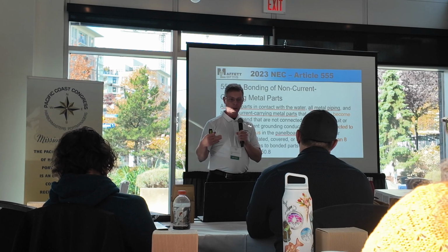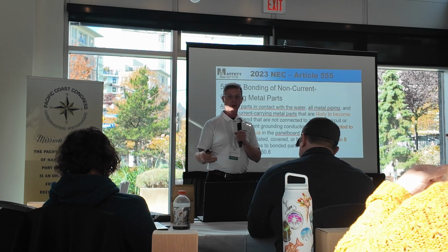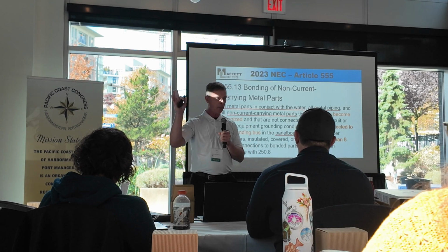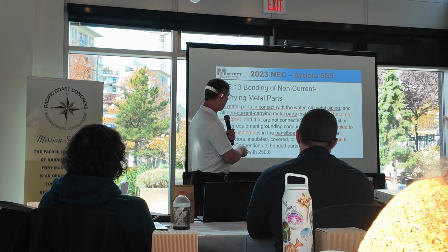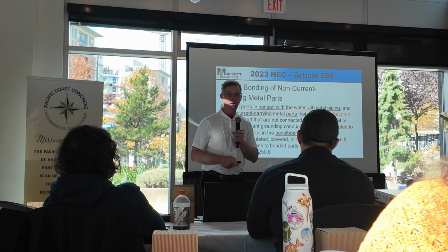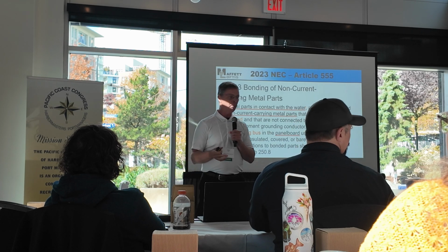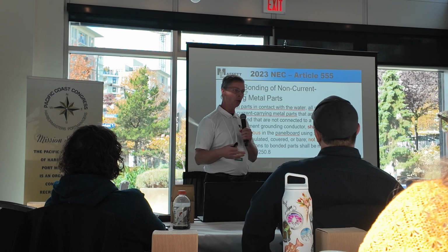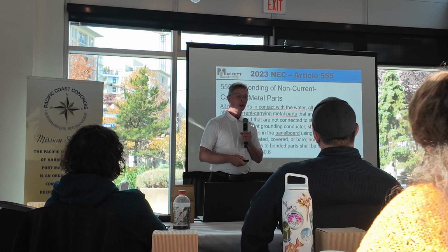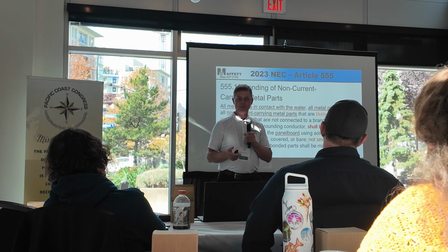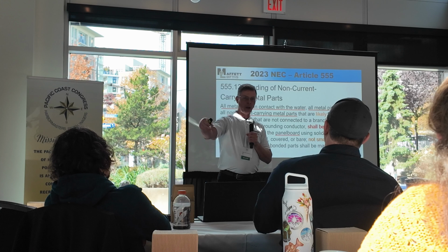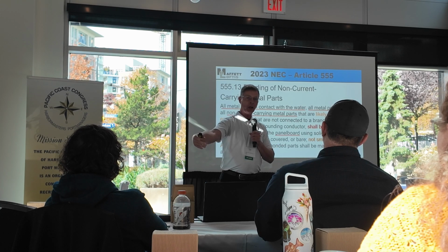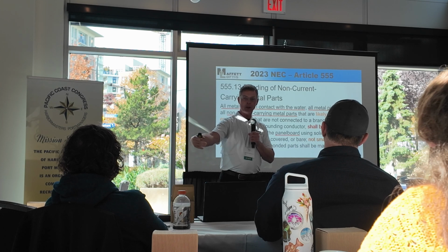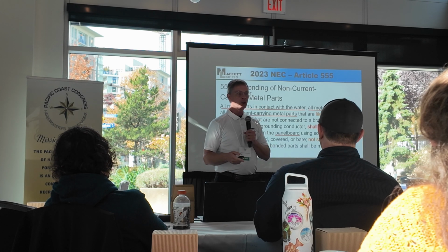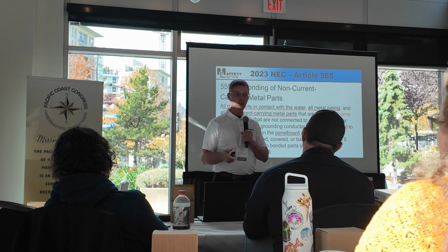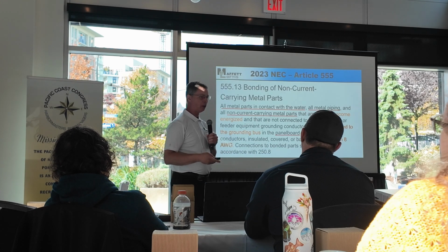And I've written articles about it and written to city governments down there trying to help some of my clients and said, no, that's not the intent of the code. I'm on the code making panel. That was not the intent of the code. The intent is that if parts in contact with water were likely to be energized, then they would need to be bonded. And rightly so, because if they could be energized, then you'd want them bonded so that if they did become energized, it would create a fault current and trip overcurrent protection. And this even includes aluminum ladders. If you had a timber frame dock and an aluminum ladder on the end of a finger, and all the wiring methods were at the main walkway, there's no way that ladder was going to be likely to be energized by the electrical system. But the electrical inspectors were requiring that ladder to be bonded, which to me makes it more likely to be energized. So I disagree with that interpretation because that was not the intent of the code.